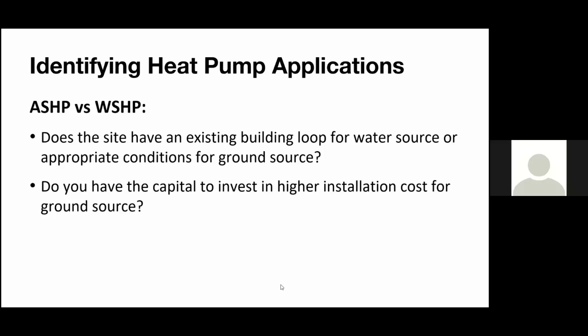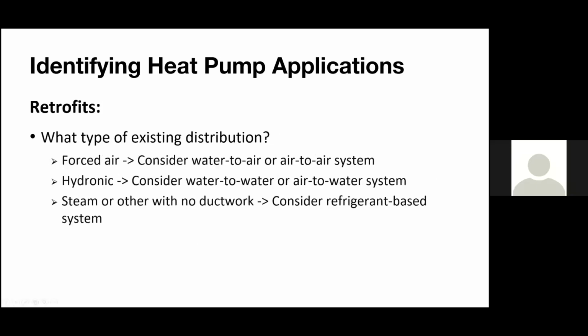So in terms of retrofit applications, just on the next slide here, a forced air system, or what type of existing distribution? That's a question. A forced air system, which is usually a machine that will move air, whether that's a vertical air handler or a horizontal air handler, and you're looking to go with heat pumps, then you could look at the water to air heat pumps. Those are your typical water source heat pumps, like I already spoke about earlier. Those are still forced air systems.